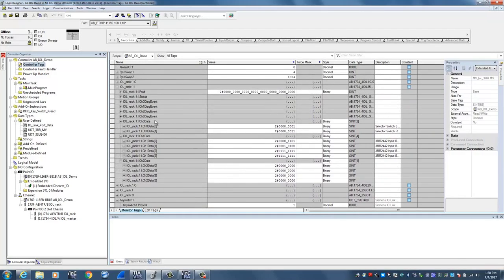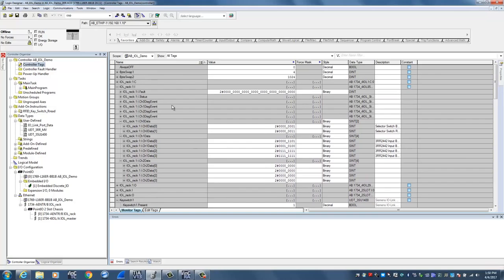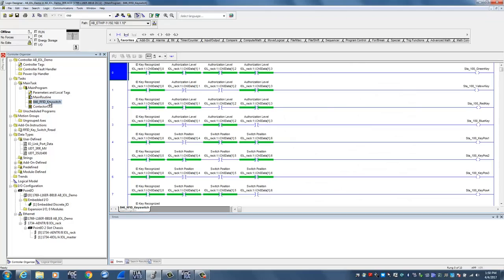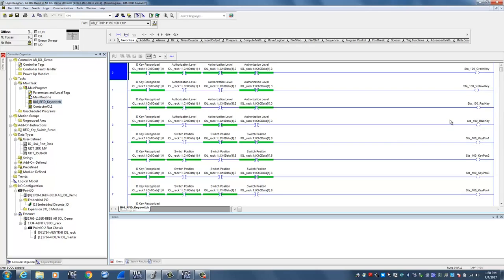The way you actually get the information is using the message command. So if I expand on my main program to a subroutine here, you'll see at the top of this subroutine several lines of logic using the cyclic data from the RFID key switch that at first discerns what color of key stick is actually inserted into the device—a green, a yellow, a red, or blue key—and then turning the knob on the reader device will allow the operator to now select different levels of access. And this next four lines of code determine what level of access has been selected.